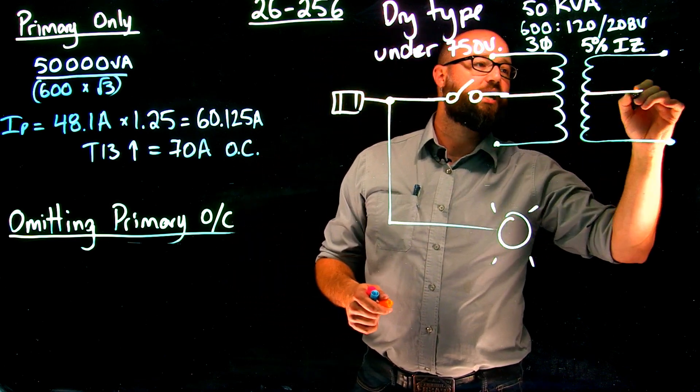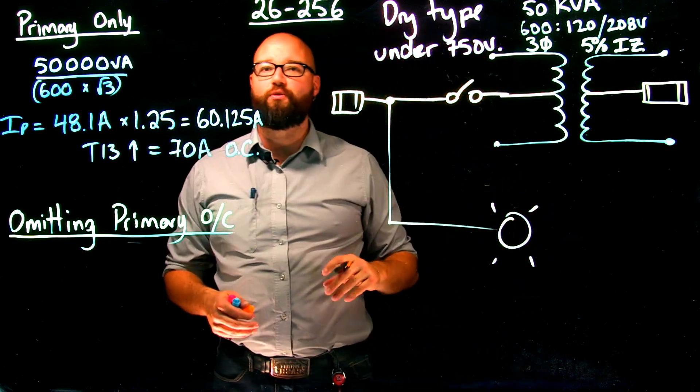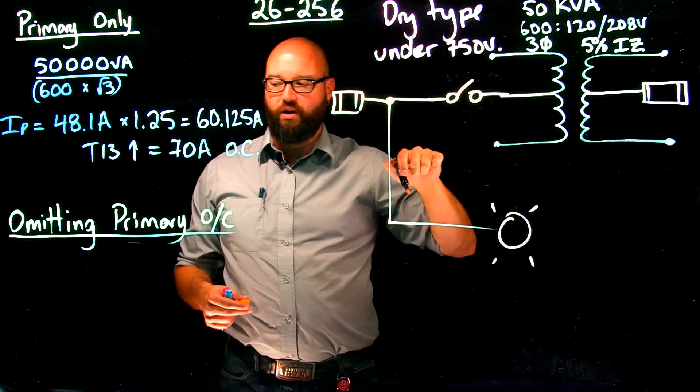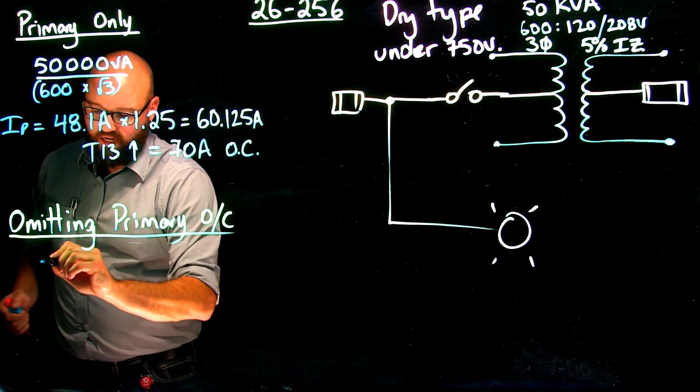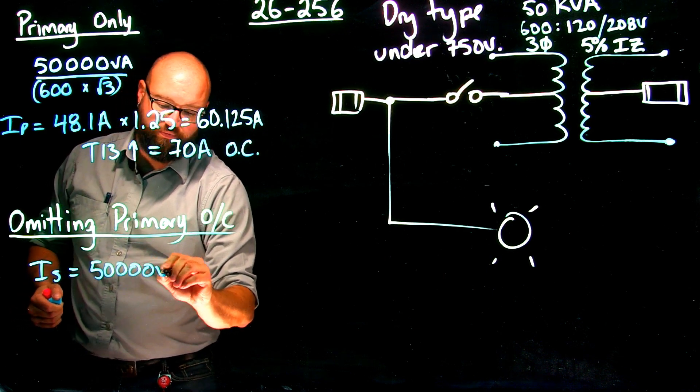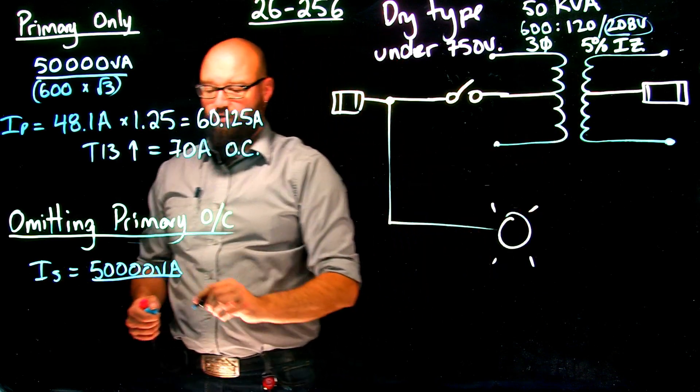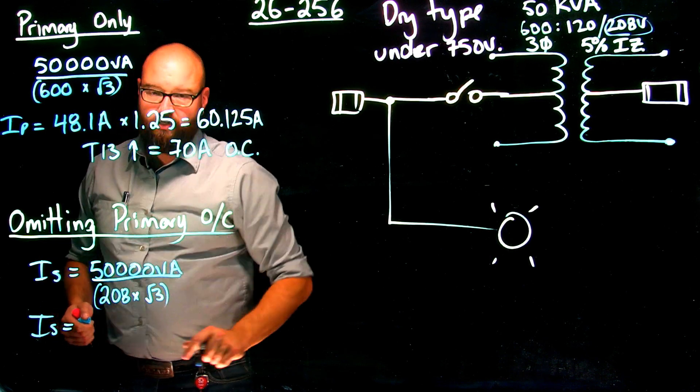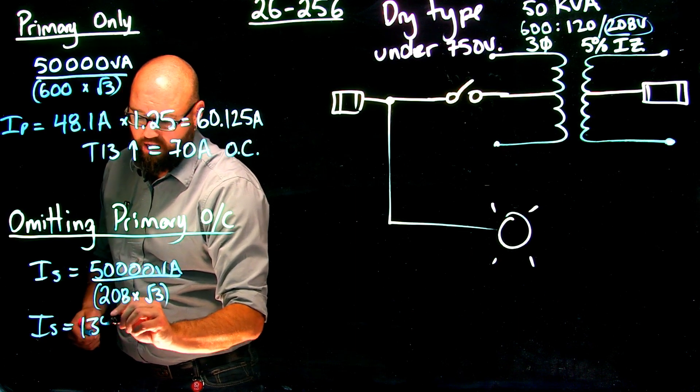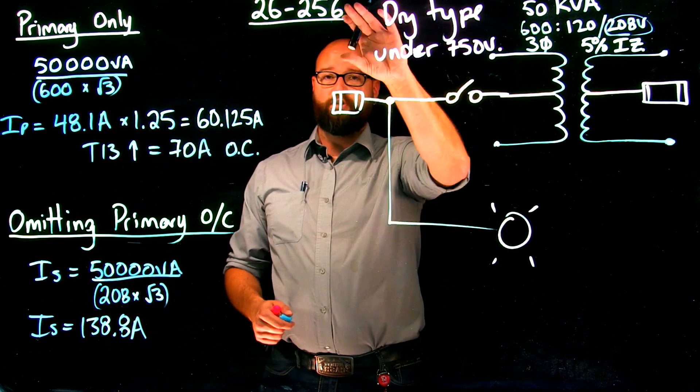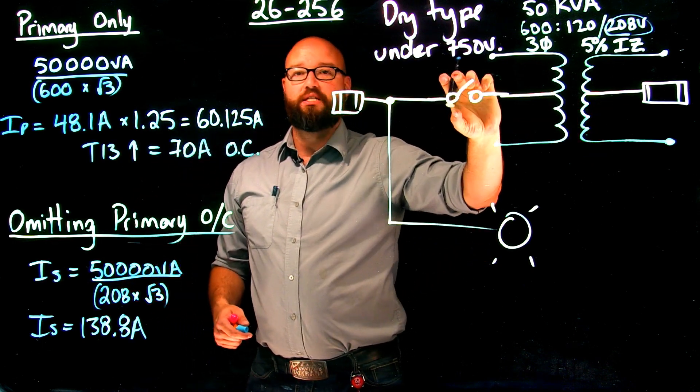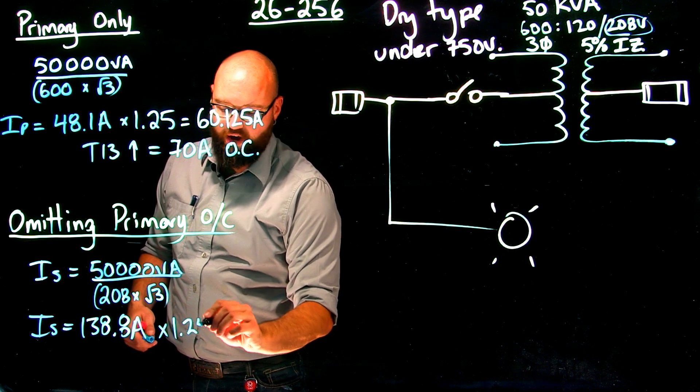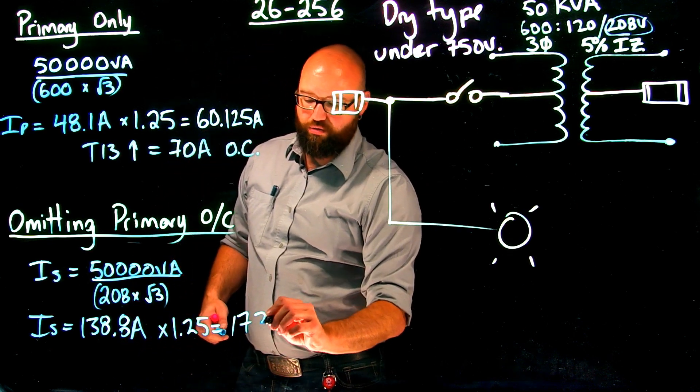And again, it doesn't matter whether it's a breaker or a fuse in this rule, that is set at not more than 125%. So we're going to need to figure out what is our rated secondary current here. So we have current on the secondary is 50,000 VA divided by my secondary line voltage of 208 volts. I end up with current on the secondary is around 138.8 amps. And as we've just read in that rule, to omit this, I have to have a secondary overcurrent set at not more than 125% of rated secondary. So times 1.25 gives me a maximum rated value of 173.5.